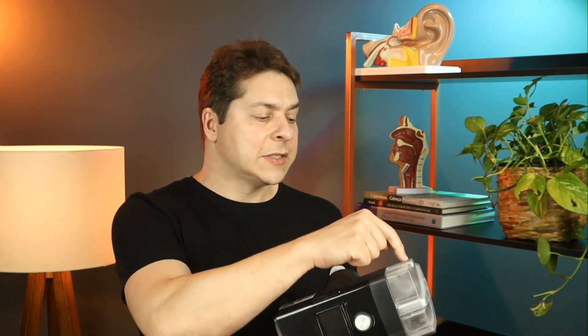It takes the air from the environment, the air enters the CPAP, and before entering it will pass through a barrier. The first barrier is a filter. Usually they have one or two filters that have to be changed periodically. And the air enters the device and inside it will be turbinated, let's say. It will gain a greater pressure and this pressure will pass through a hose and reach a mask that will reach your nose. But before it passes through this hose, before it reaches you, the patient, it will be moistened.